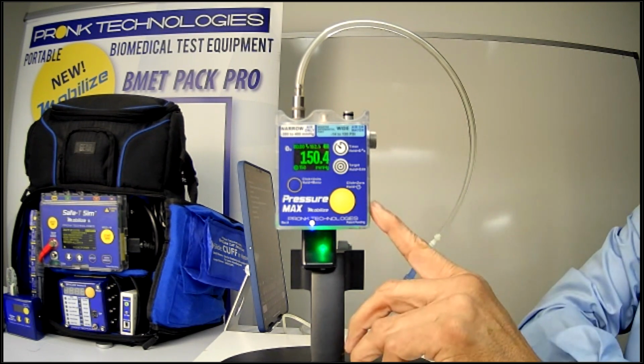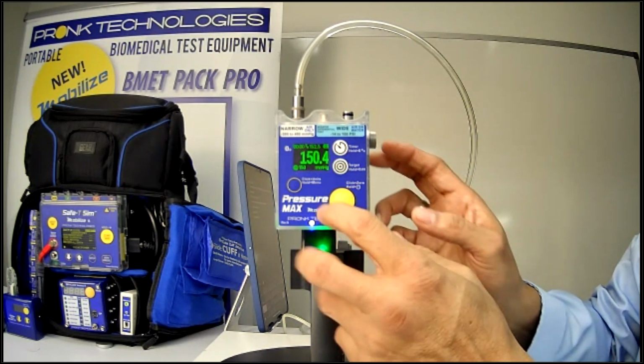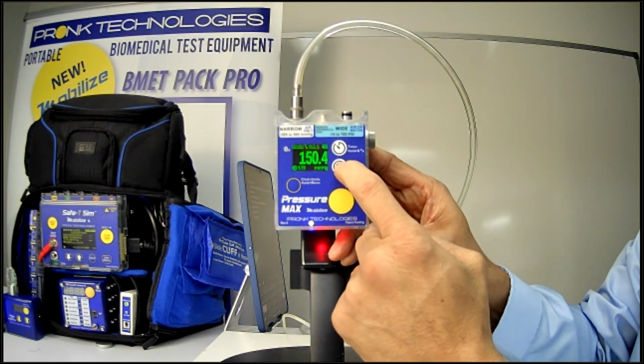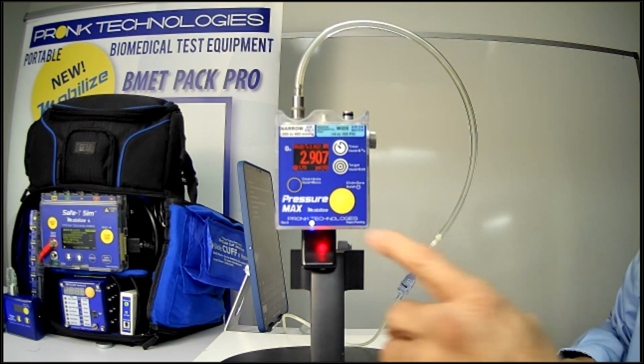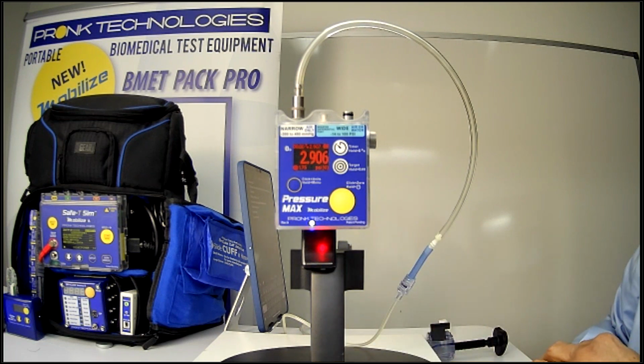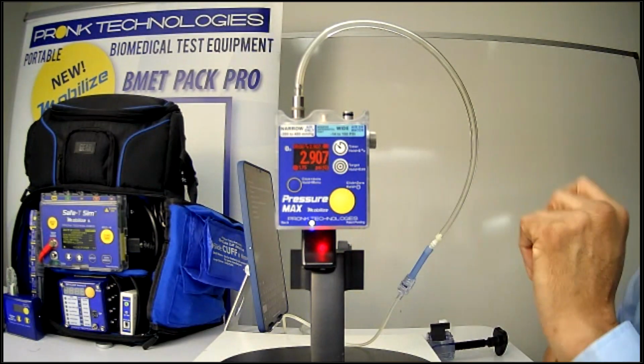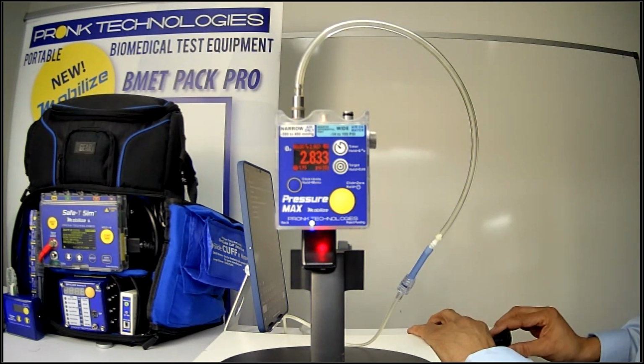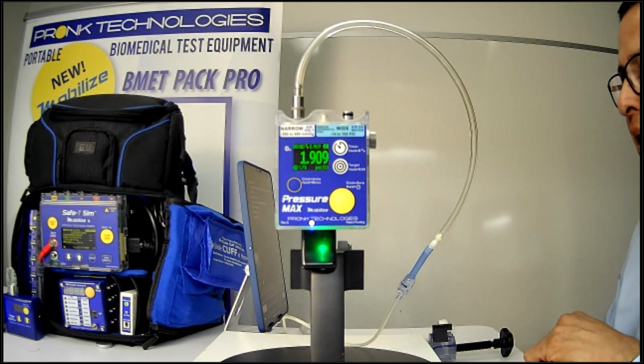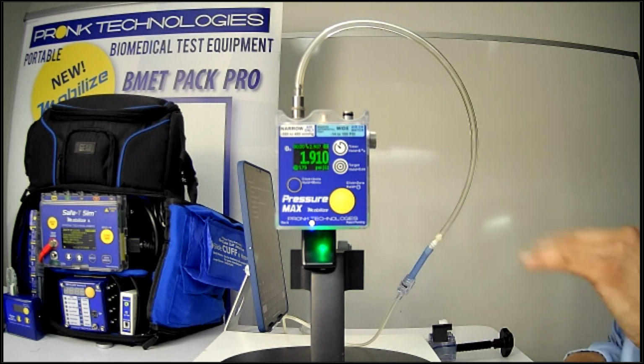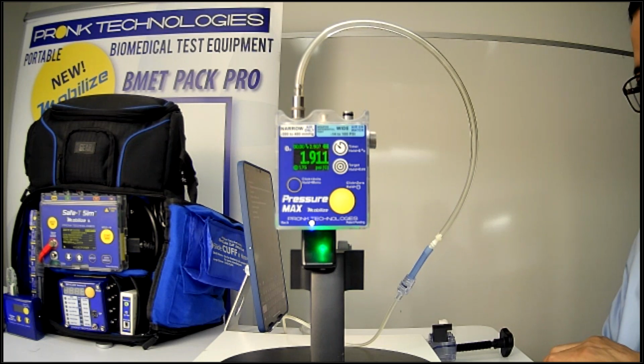It's a nice feature that was really input we got from the field, to help aid in knowing that the result is within the target pressure that was designed. So you can program into the unit 5 different pressure targets, and I can select them from here. If I tap on this button again, you'll see I've now selected a different pressure target, and my target pressure there is 1.75, in the unit of measure PSI. Clearly the unit is illuminating red because I'm over the target, and if I adjust my pressure down to get within range, then it will illuminate green when I'm within that target. For this particular target, I believe I programmed it for plus or minus 0.25 as my tolerance. So you have full control over the target and the tolerance that you want to program, having that pass/fail defined on the unit, again saving you time and making it easy to verify your pressure is within the target.